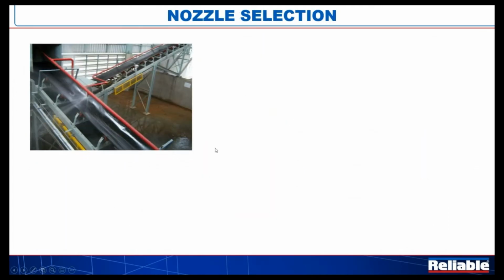So how do we select the nozzle? We select the nozzle, as you might expect, by what it is we're trying to do. In the case of, let's say, moving coal down a conveyor, I really don't need to throw a lot of velocity onto that coal. Let's assume that it's burning coal, and I don't want to blow it all over the floor. So we really want to throw enough water on that moving material, and that's typically done with, let's say, a low velocity nozzle fire sprinkler.